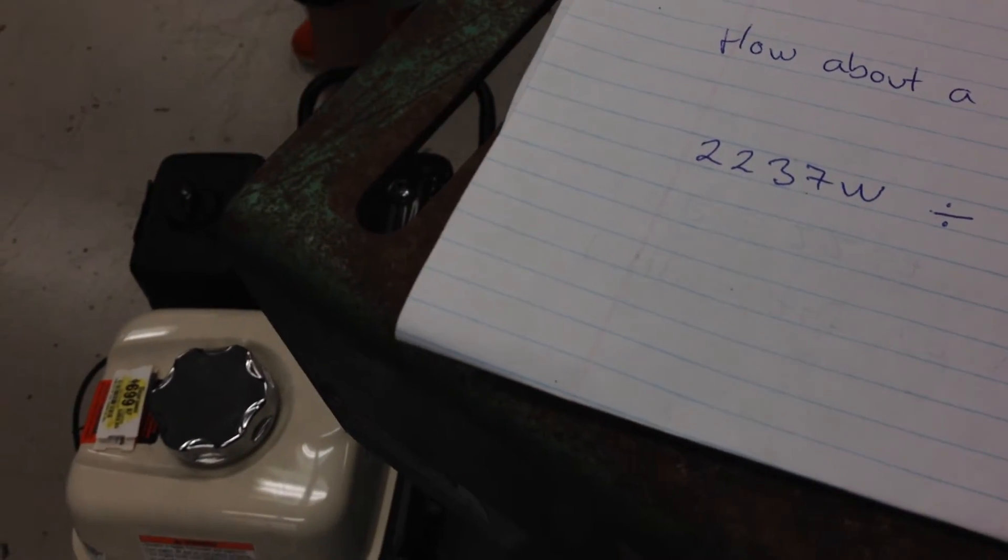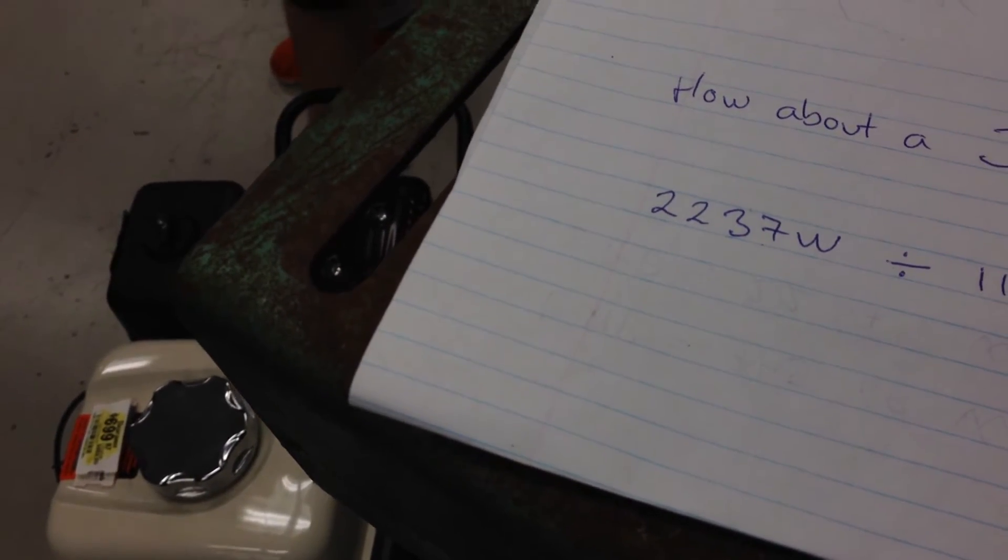They say it's 14 on the back. On the back it says 14 amps. The 14 amps is not making sense with the three horsepower. The math is just not adding up.